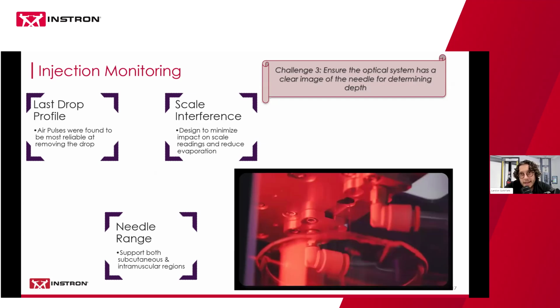In most cases, after an injection, there's a drop of fluid left at the tip of the needle, and it's important to remove that to make sure it's not counted towards your needle depth. So we did a significant amount of testing to really validate what profile of air works across a range of needle lengths, needle gauges, and fluid viscosity. That was a lot of work to develop.